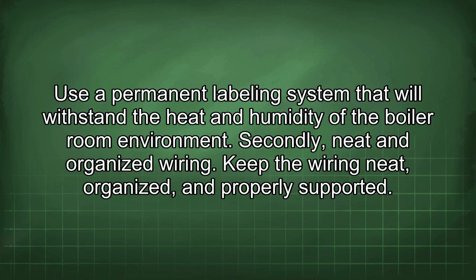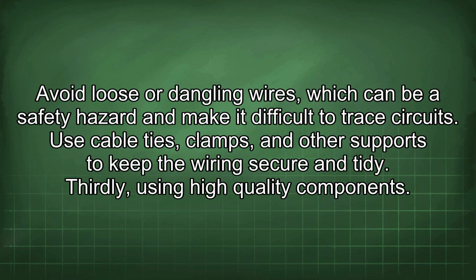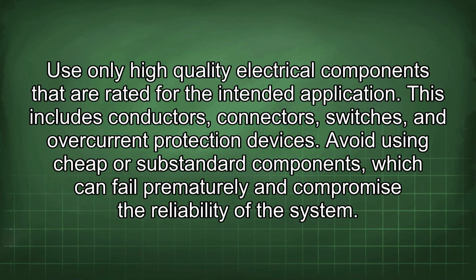Secondly, neat and organized wiring. Keep the wiring neat, organized, and properly supported. Avoid loose or dangling wires, which can be a safety hazard and make it difficult to trace circuits. Use cable ties, clamps, and other supports to keep the wiring secure and tidy. Thirdly, using high-quality components. Use only high-quality electrical components that are rated for the intended application. This includes conductors, connectors, switches, and overcurrent protection devices. Avoid using cheap or substandard components which can fail prematurely and compromise the reliability of the system.